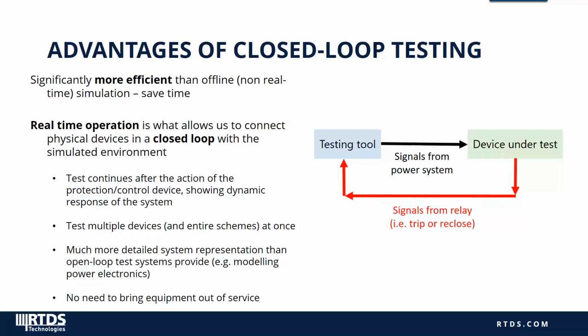So closing a loop means not only observing the response of the device to an imposed signal, but also interfacing that device's response back into the simulated network. And this type of testing, also called hardware in the loop testing, is only possible if we are updating the inputs and outputs of our simulation continuously in real time. It's not possible with an offline simulation or with open loop testing tools like a relay test set. While test sets will remain an important tool for supporting the commissioning process, they lack the flexibility to test multiple devices at once or to allow for detailed modeling of the network, for example, power electronics.